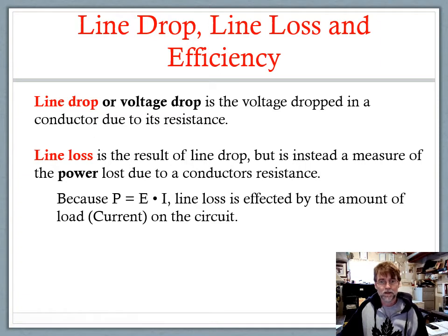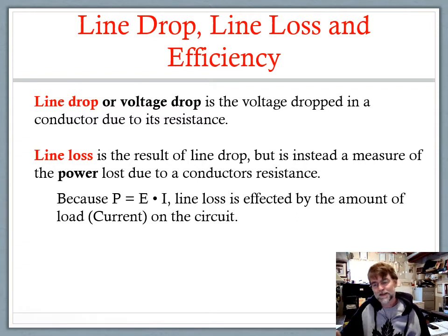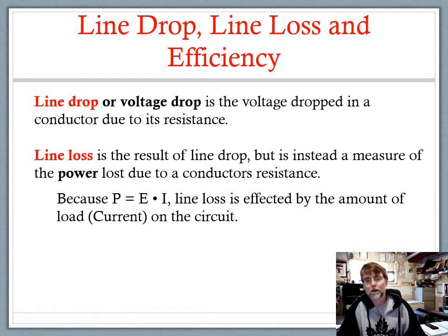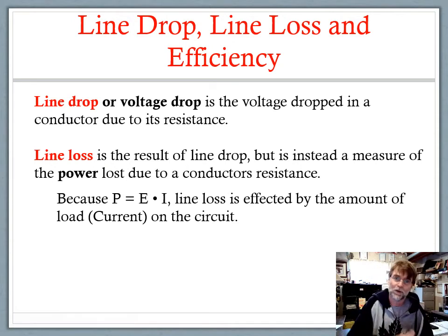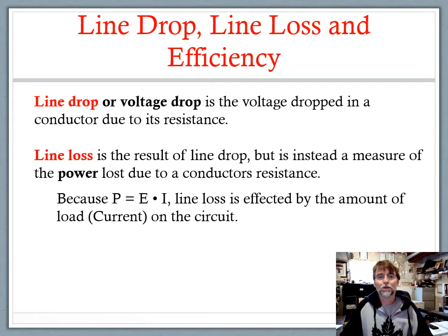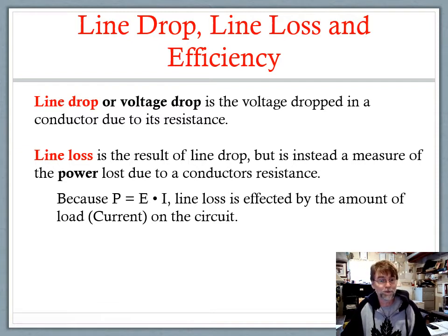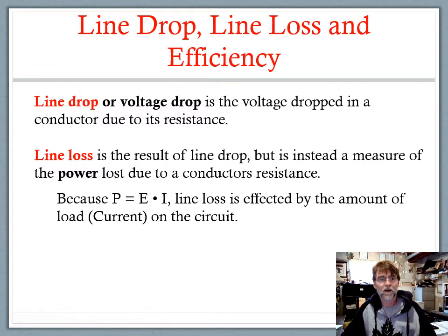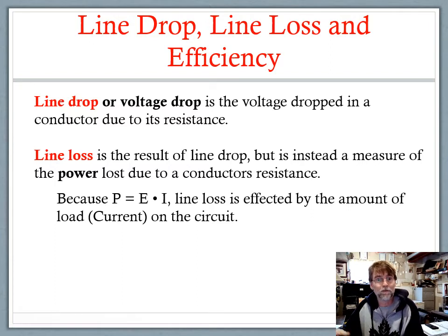Because P equals E times I, line loss is affected by the amount of current. The voltage is a consistent value — whatever the power supply offers is what it offers. But as electrical loads are plugged in or disconnected, turned on or off, the amount of current in the circuit continues to vary. Because power is voltage times current, as you increase the current in the circuit, you increase the amount of power being lost. When we talk about line loss, because it's a power conversation, we're really going to focus on the current draw of whatever loads are plugged into the circuit.